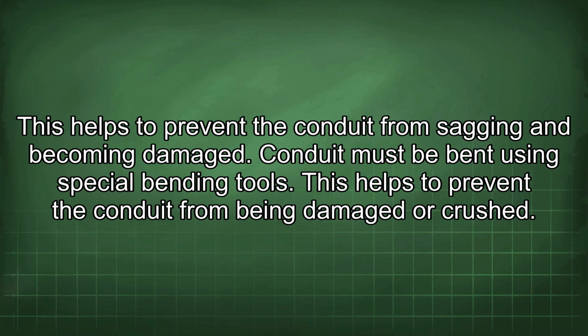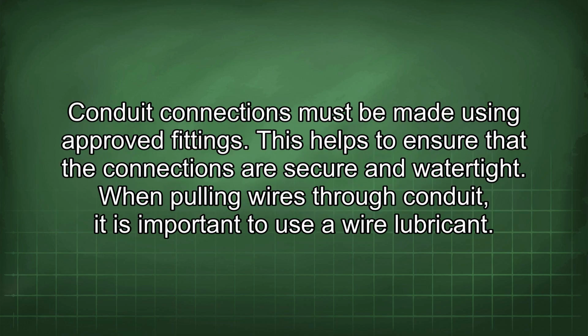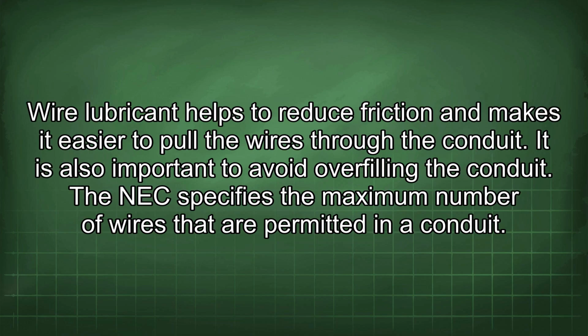Conduit must be bent using special bending tools. This helps to prevent the conduit from being damaged or crushed. Conduit connections must be made using approved fittings. This helps to ensure that the connections are secure and watertight. When pulling wires through conduit, it is important to use a wire lubricant. Wire lubricant helps to reduce friction and makes it easier to pull the wires through the conduit.